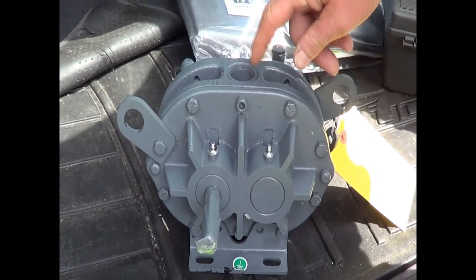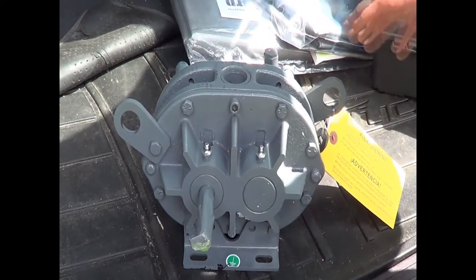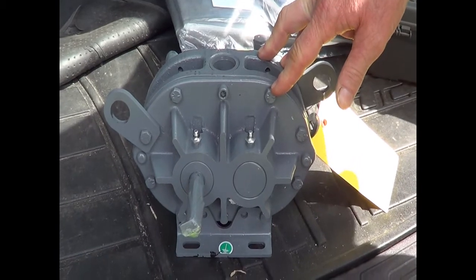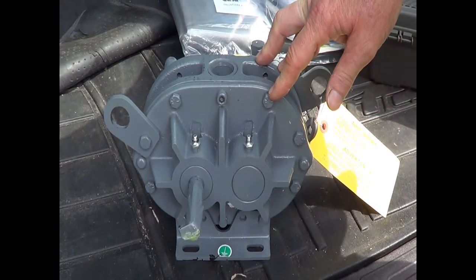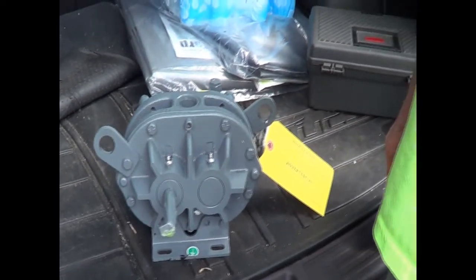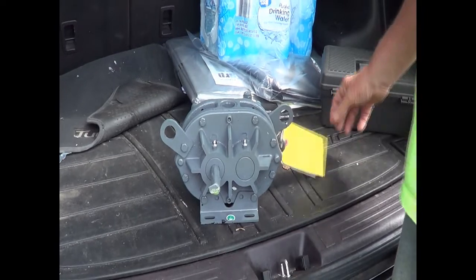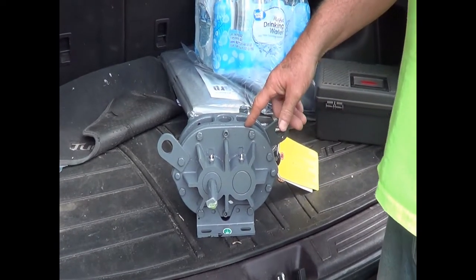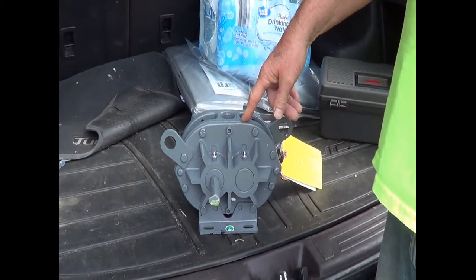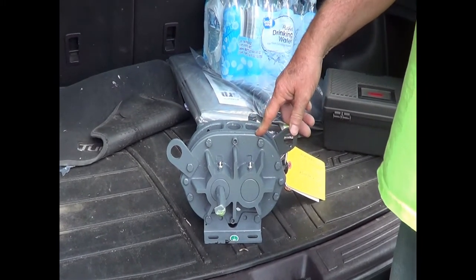Making sure the air filters are clean. These units are going to be changed — they're being moved outside. They're in a very dusty, harsh environment for a compressor. It's terrible. That's half the problem; the other half is the heat. The conditions are terrible and they should never have been put in this situation. You're going through these fairly regularly right now.